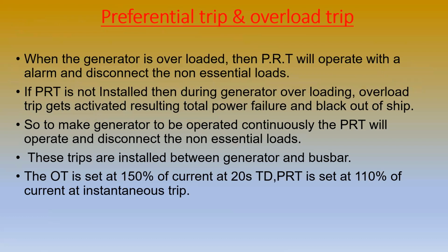So next is the preferential trip and overload trip. Whenever the generator is getting overloaded, the preferential trip will operate, and that will give an alarm as well as disconnect the non-essential loads. If the preferential trip is not installed, during generator overloading the overload trip will get activated, resulting in total power failure. When the overload trip is activated, it will be a total shutdown of the ship. When the preferential trip is activated, it will stay connected to the essential loads, and the non-essential loads are disconnected. So to keep the generator operating continuously, the preferential trip relay will operate and disconnect the non-essential loads.